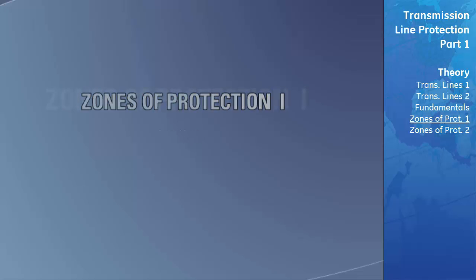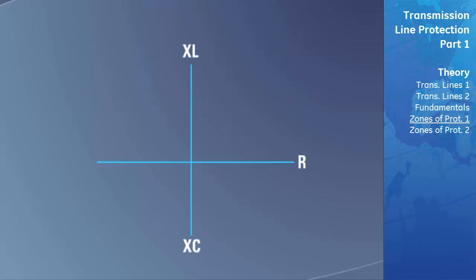To program distance relays, you need to configure the impedance of the line where any impedance less than this value will indicate a faulted line. This is done in modern distance relays by creating zones of operation on the RX diagram. If the impedance calculated at the point of measurement of the power system ever falls within this zone, the relay will trip. These zones fit into the following operating characteristics.